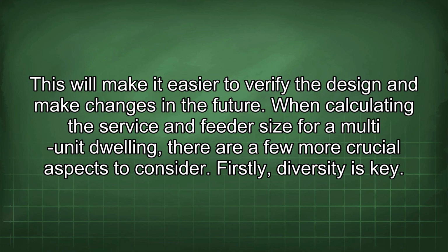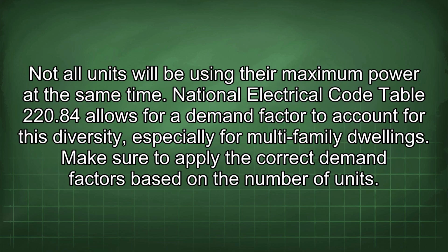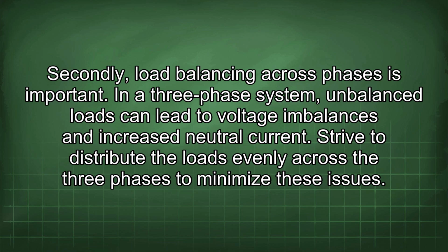When calculating the service and feeder size for a multi-unit dwelling, there are a few more crucial aspects to consider. Firstly, diversity is key. Not all units will be using their maximum power at the same time. National Electrical Code Table 220.84 allows for a demand factor to account for this diversity, especially for multi-family dwellings. Make sure to apply the correct demand factor based on the number of units. Secondly, load balancing across phases is important. In a three-phase system, unbalanced loads can lead to voltage imbalances and increase neutral current. Strive to distribute the loads evenly across the three phases to minimize these issues.